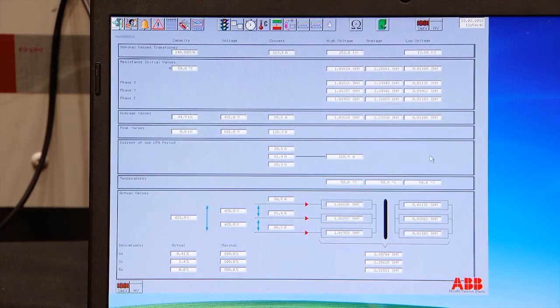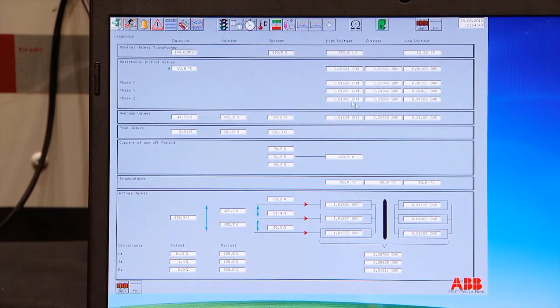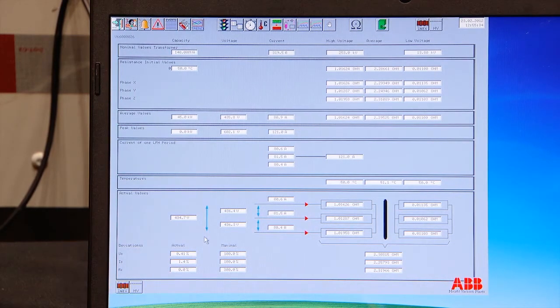On the resistor page, we still have our initial resistances. At the bottom part we have the actual resistances. Since we are only running in average mode, which is 0.7 Hertz in this case, we are only updating the average resistance. The high voltage and the low voltage resistances will be updated later when we stop heating, take the high voltage, low voltage measurement. That's when the new values are coming. So that reading is coming 5 degrees before our set point in temperature. The set point is 65 degrees, 5 degrees before is 60 degrees.